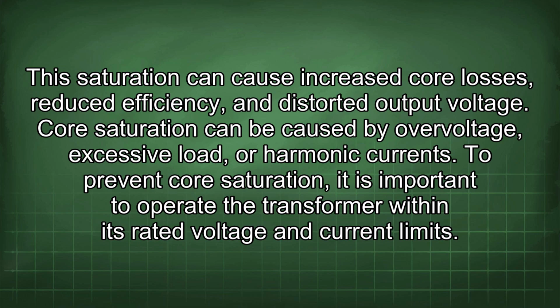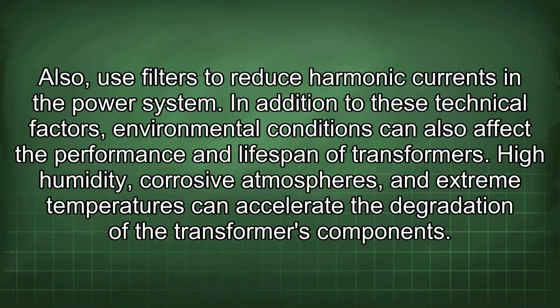Core saturation can be caused by overvoltage, excessive load, or harmonic currents. To prevent core saturation, it is important to operate the transformer within its rated voltage and current limits. Also, use filters to reduce harmonic currents in the power system.